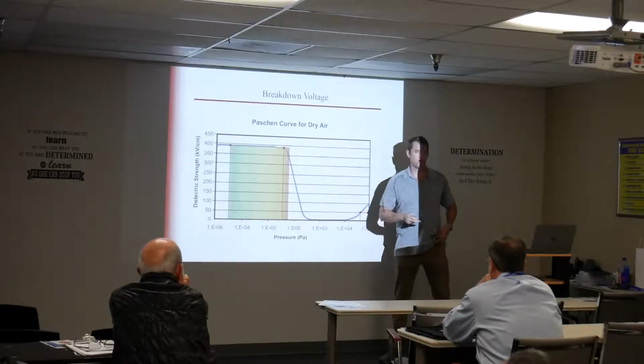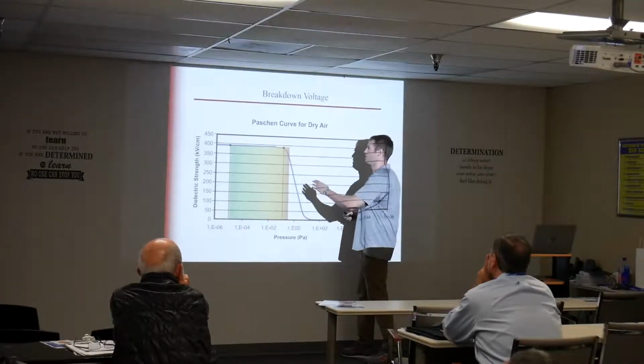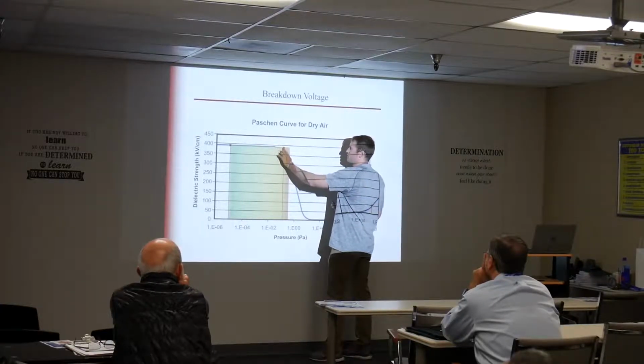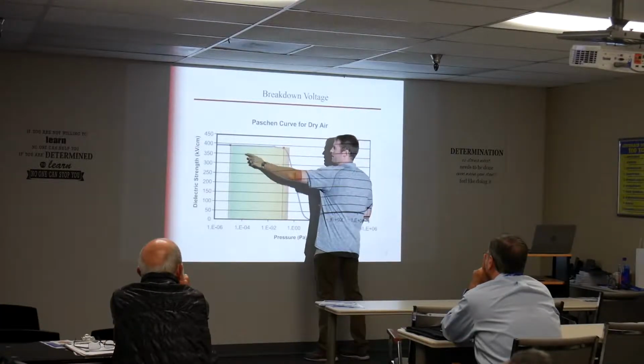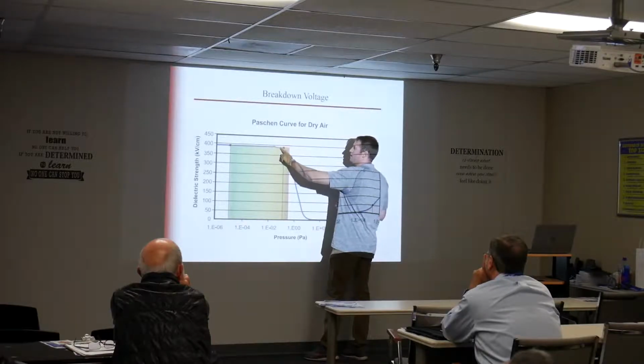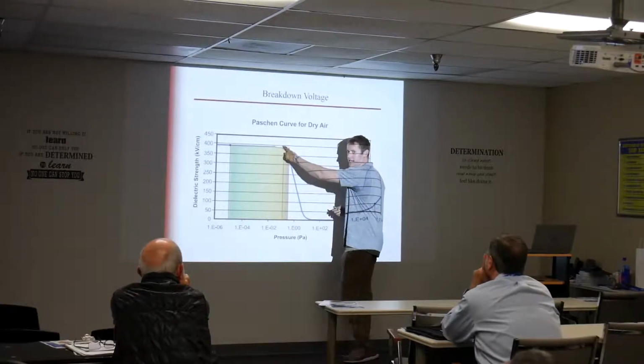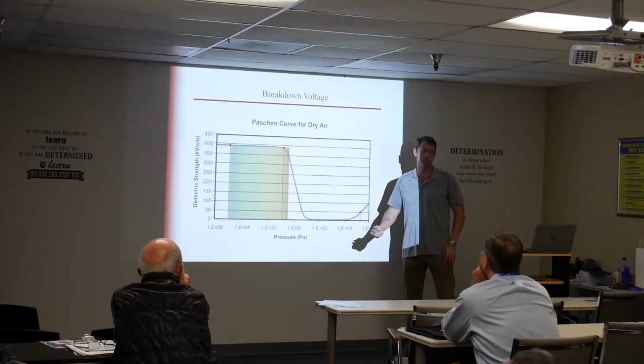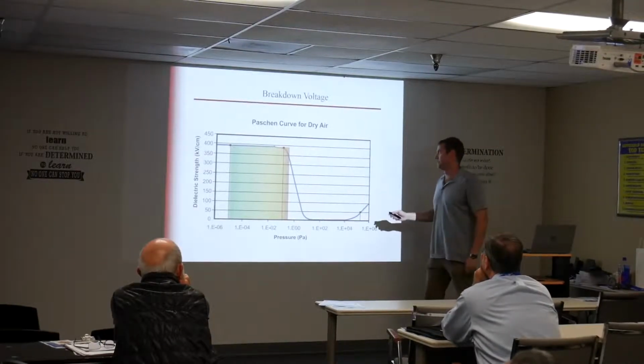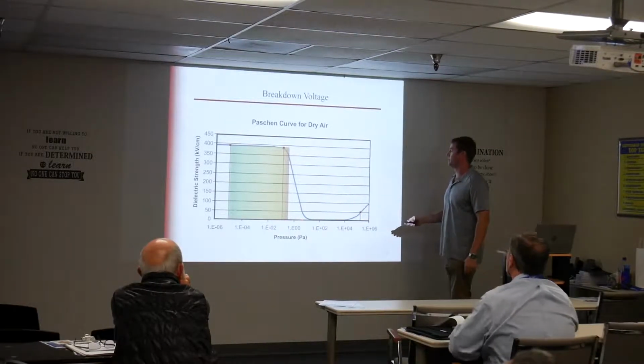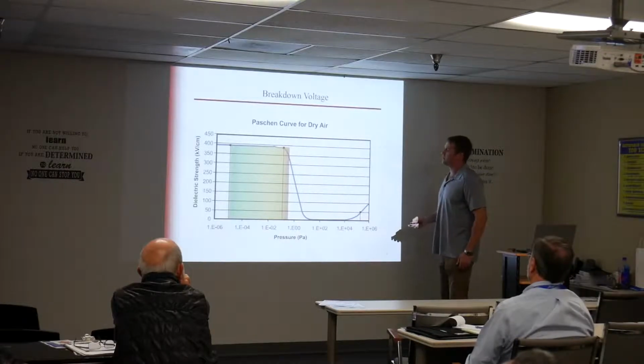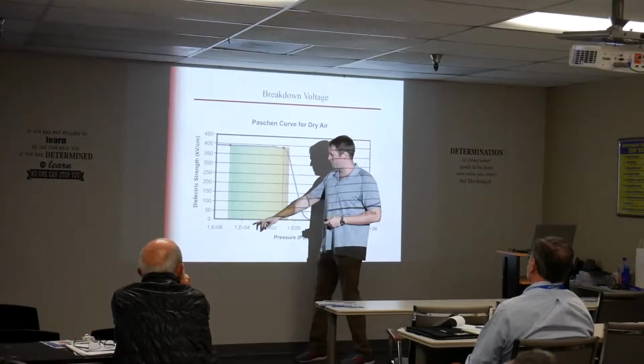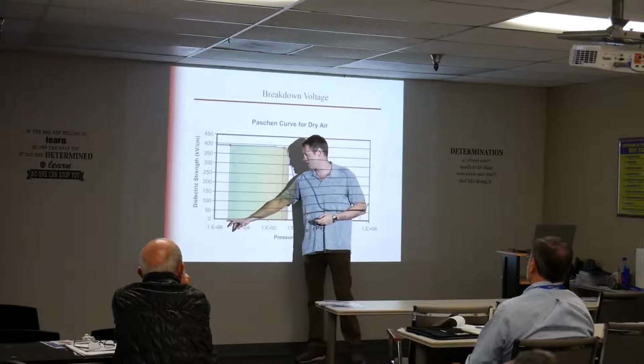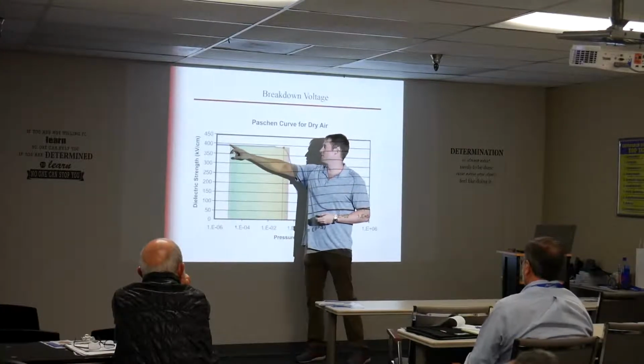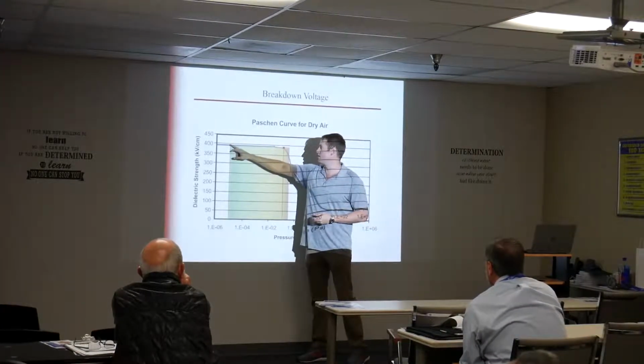Before, when you high potted a bottle and it passed, all that told you was that I'm somewhere to the left of that red line. But I don't know if I'm here, or you could be right there and it'll pass high pot and you have no idea. Put your sticker on and say it's good, and then in a year or two it's going to fail. So that's the benefit of our test. This is where a brand new interrupter starts off, at 1 × 10 to the -5. Like I said, from here to here is 20 to 30 years.